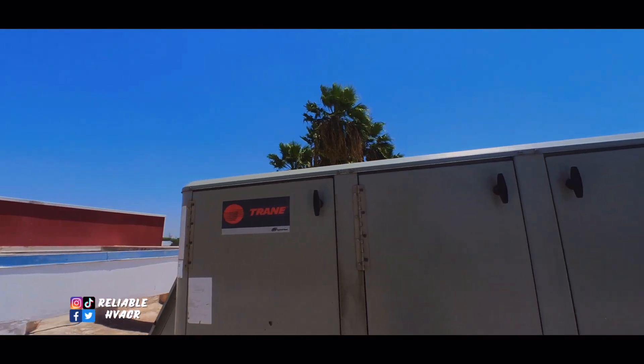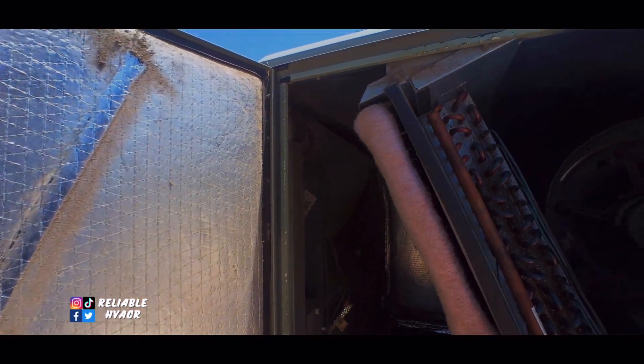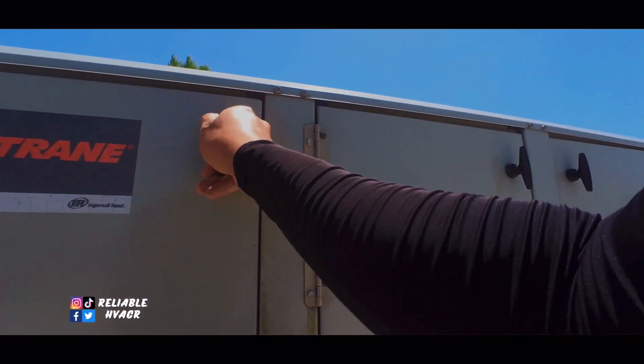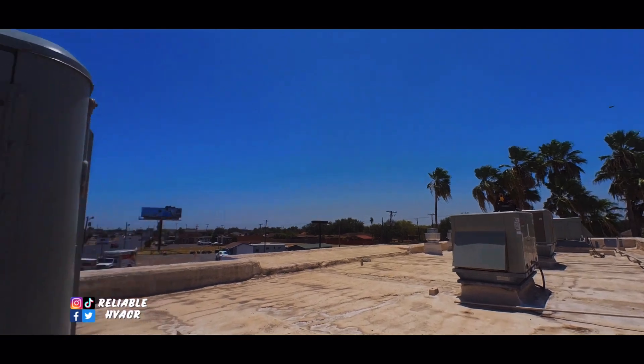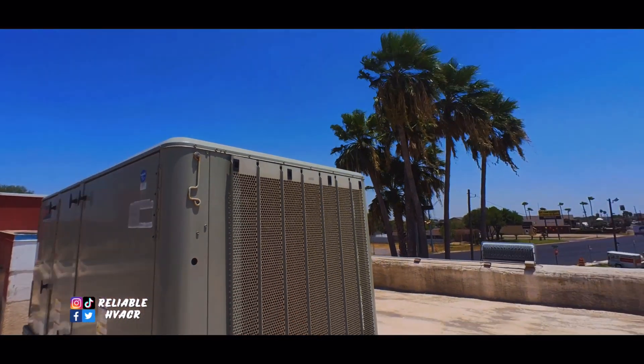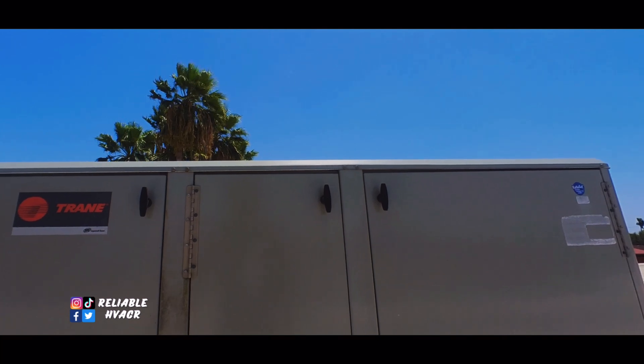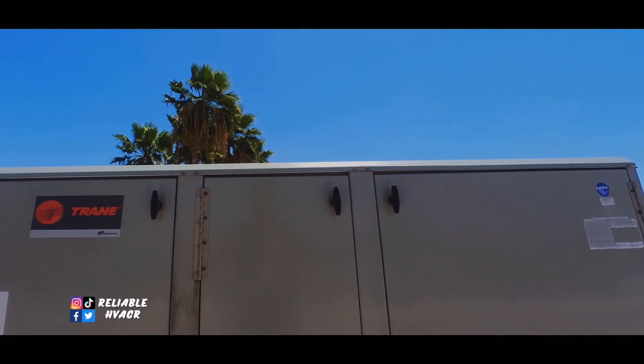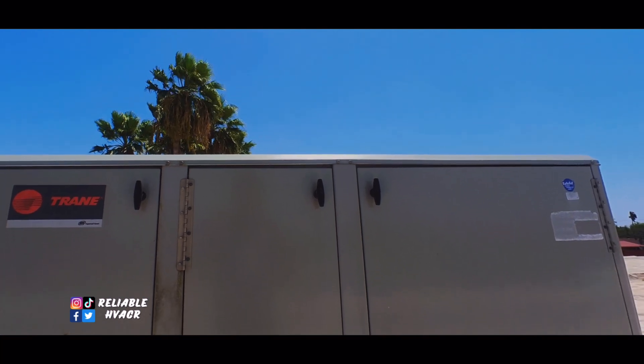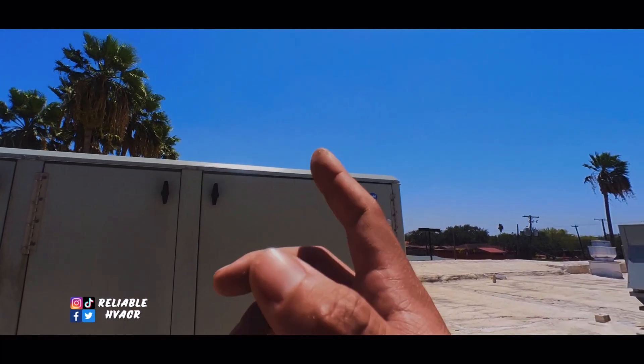About the lobby - this is technically the lobby and the dining. So this is sweating. Lower grid evaporator is cold. Filters are okay. But if we have a dirty condenser, it's not gonna be running efficiently. So that suction line is mildly cold, not sweating. On this one we got a micro channel, so we got to clean that out. And this one's not gonna ever work efficiently because it's installed backwards. Over here is actually where the supply vents are, and the supply blower is blowing air through the return grill. There's no easy way to fix that - we need a curb adapter to fix this one.